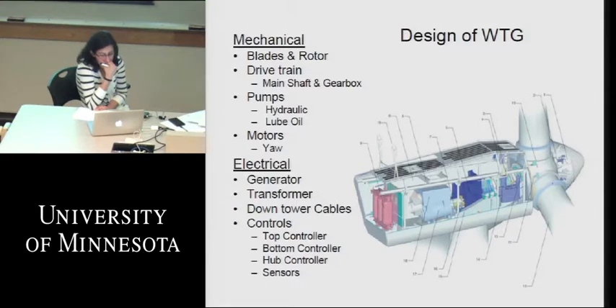And lastly, there are lots and lots of sensors on these wind turbines. There are around 1,200 different types of sensors. Obviously, thermal sensors, pressure sensors, strain gauges, accelerometers, flow sensors, filters, that sort of thing, filtering and detection systems that all feed into the top controller and a condition monitoring system we have installed in these modern wind turbines. Okay, next slide.